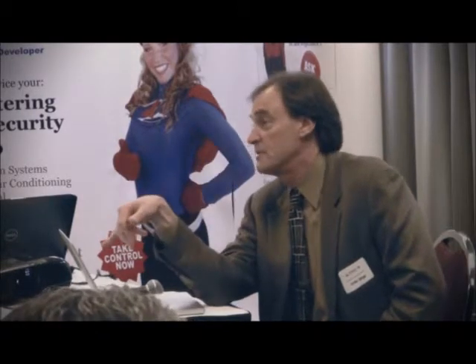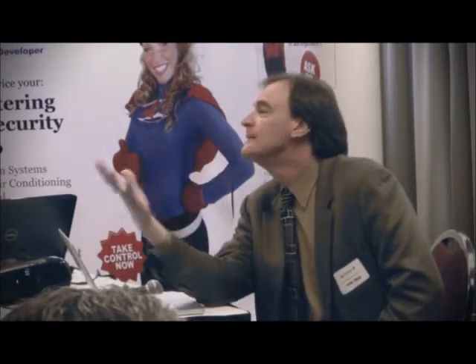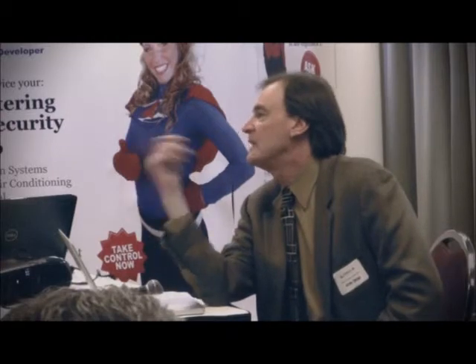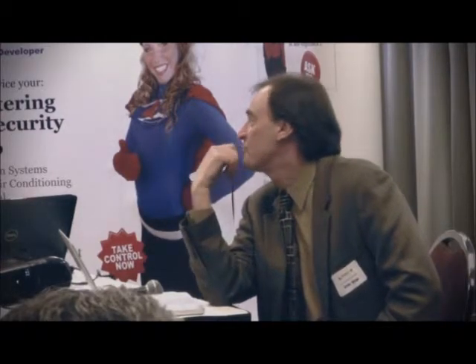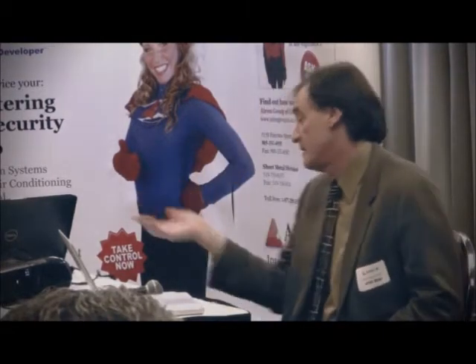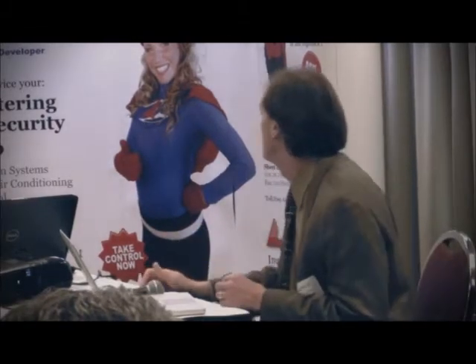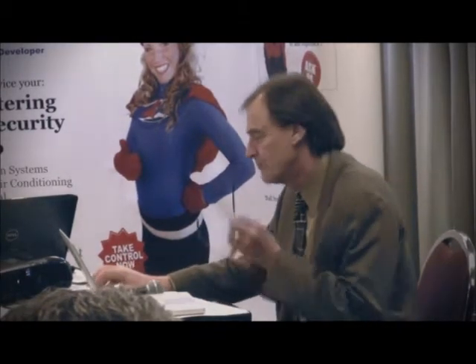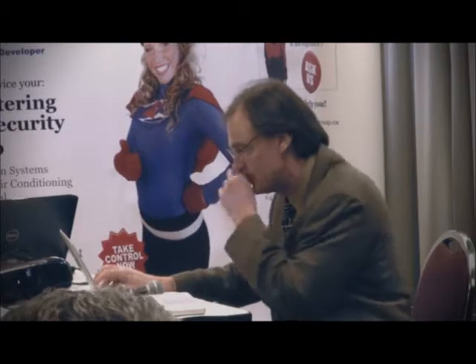They were able to use this data — this was in Wisconsin — to go to the power company and actually get a check, converting to gas-fired humidification because of this, since the power company didn't want the spikes either. No one would have ever seen this without the insight that came from the data; otherwise we'd have just kept running it the way it was running. It had not only a peak demand benefit but an overall energy saving too. So that's just an example of how this gets used.